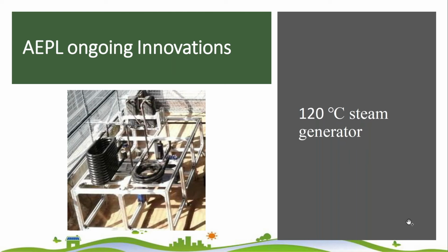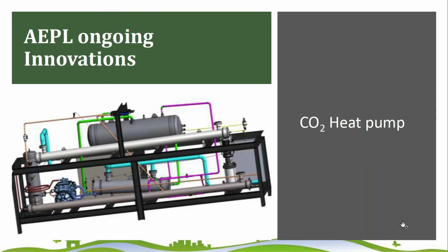So next slide. The next innovation that is going on is the CO2 heat pump, and CO2 is a natural refrigerant. Hence, it is the best eco-friendly refrigerant that can be there. The only problem with CO2 heat pumps is the high pressures, and how we have to deal with and maintain them. So the complexity in building the machines exists, and the cost of the compressor is also more. But the payback period will be less, since the COP will be around 6.5.